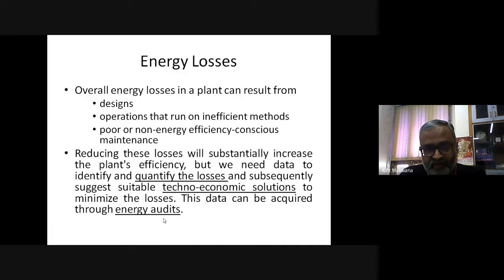Now, this is the difference. For any reason, what we design and what the actual operating conditions are - there is a gap between the two, and we have to identify this gap, because this gap means a transformer of 500 kVA is supplying a load of only 200 kVA. So this is the mismatch, and there are so many such mismatches you can find in any industry. This is a big issue.